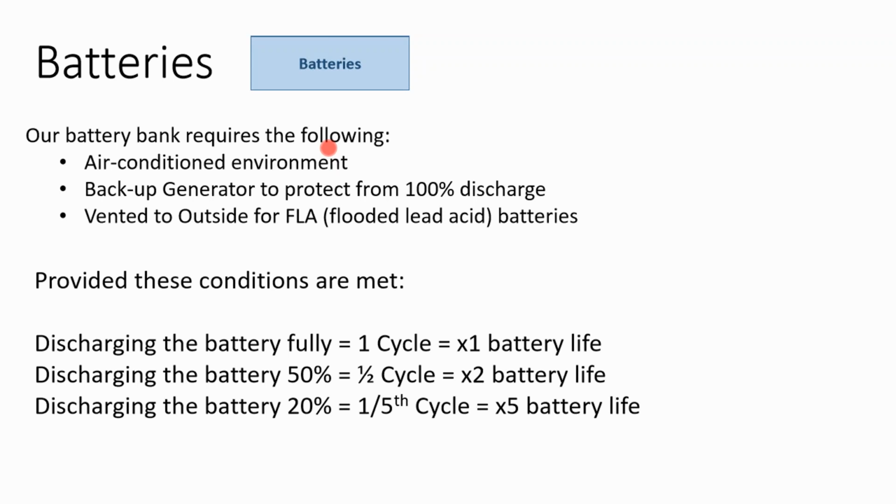When you run up at the float phase, when you run the conditioning and you're overcharging the battery, that's when you produce the gas. And so you can't do that maintenance on these maintenance-free batteries that are sealed up, because they would produce too much gas, and that wouldn't be good for the build of the battery. So basically, with these maintenance-free lead-acid batteries, there's no free lunch. They have shorter life and higher cost.